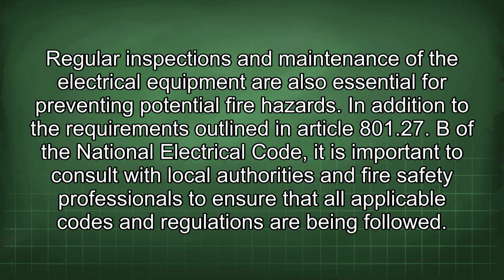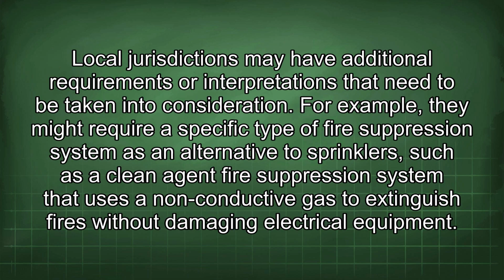In addition to the requirements outlined in Article 801.27b of the National Electrical Code, it is important to consult with local authorities and fire safety professionals to ensure that all applicable codes and regulations are being followed. Local jurisdictions may have additional requirements or interpretations that need to be taken into consideration. For example, they might require a specific type of fire suppression system as an alternative to sprinklers, such as a clean agent fire suppression system that uses a non-conductive gas to extinguish fires without damaging electrical equipment.